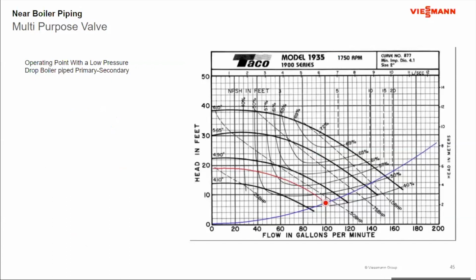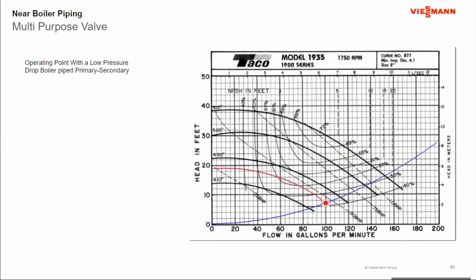So I ran one of our boilers, boiler conditions, through TACO's website to size the pump. I wanted 100 gallons a minute. And based on my calculation, at 100 gallons a minute, the boiler loop was going to have about 5 feet of head loss across it. Now, to give you an idea about what that 5 feet represents, when I ran it through, the program said no pumps were available. So the head loss was actually too low for the pump to calculate because the pump shouldn't operate down there. I was able to get it to actually run for me when I brought it all the way up to 7. So here's my operating point here.